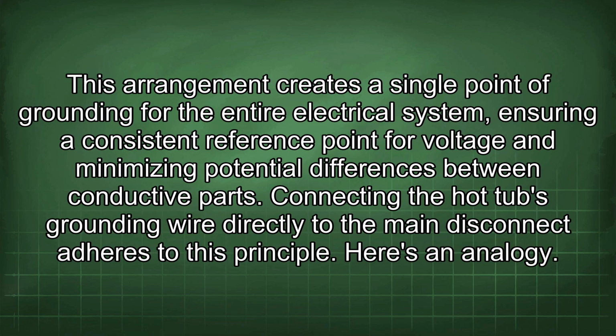This arrangement creates a single point of grounding for the entire electrical system, ensuring a consistent reference point for voltage and minimizing potential differences between conductive parts. Connecting the hot tub's grounding wire directly to the main disconnect adheres to this principle.